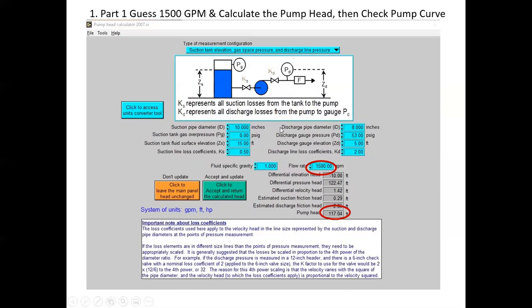Okay, so we're going to plug that in. Our suction line loss coefficient was 0.5. That's for the sharp edge entrance over here at the tank where the 10-inch pipe connects. And then the discharge coefficient was for the check valve right here, and that was 2. It's standard water, so the fluid specific gravity is 1, but we really don't know a flow rate. And so you can't calculate a pump head without a flow rate.